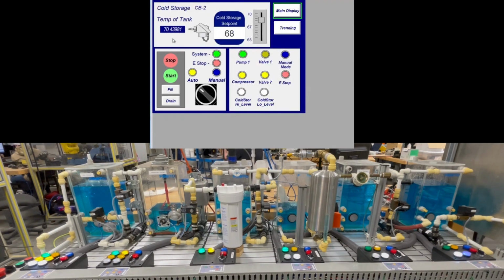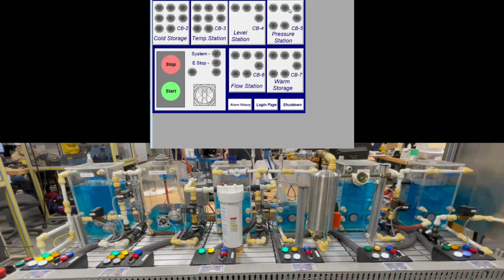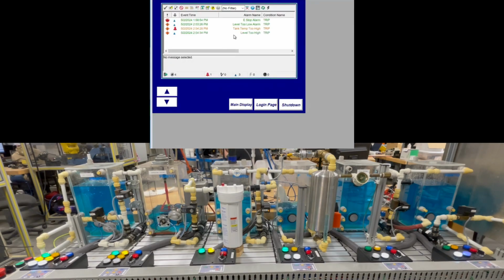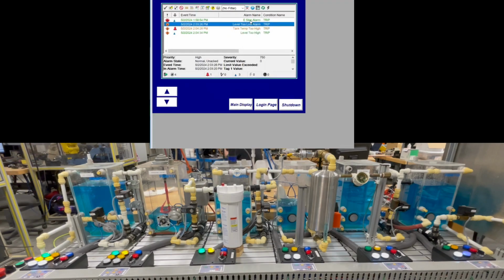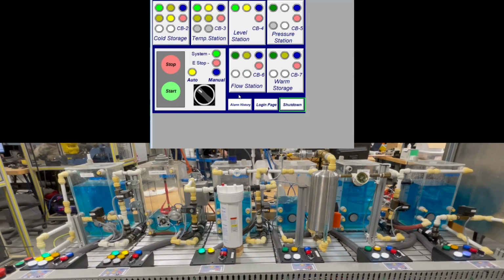And then now that the flow station is full, it will stop putting water into it, and then the pressure will drop. You'll see the PID is probably out of range. Since we were changing the level station up and down, it's going to show that the alarm went off because it was out of level, because the pump wasn't running and the station wasn't on yet.